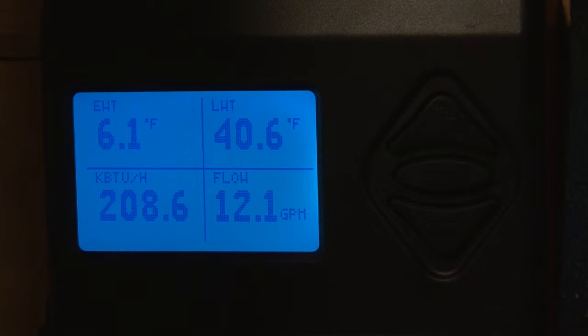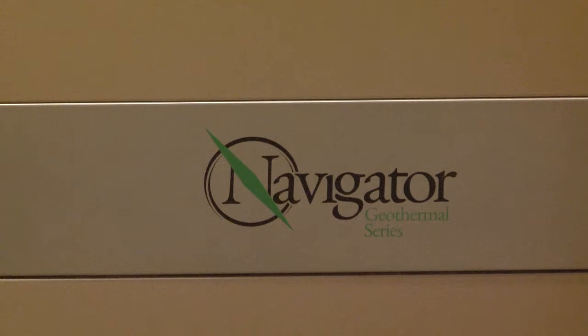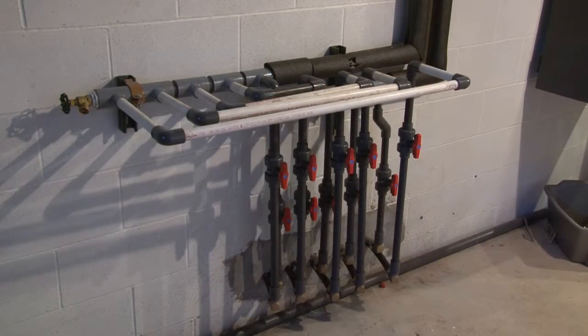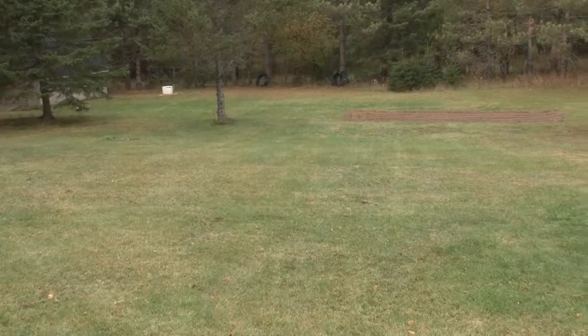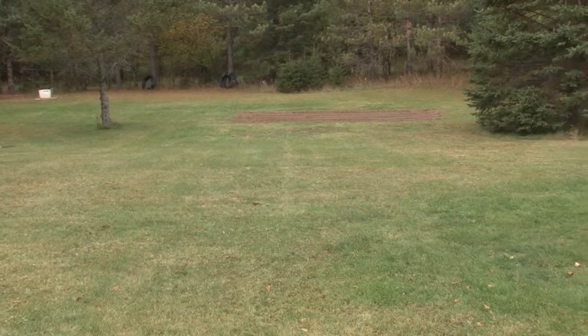We're part of the renewable portfolio because we're using indirect solar heat. We use some electricity to run our compressor, but we're getting extra energy from the ground that's stored there, and we utilize that—so we can use one unit of energy to create four or five units of energy. We're considered renewable and therefore a green technology, versus bringing gas or oil in, transporting it, combusting it, and trying to get rid of what we don't want. We're extremely efficient, using energy that's already stored right here on your property.